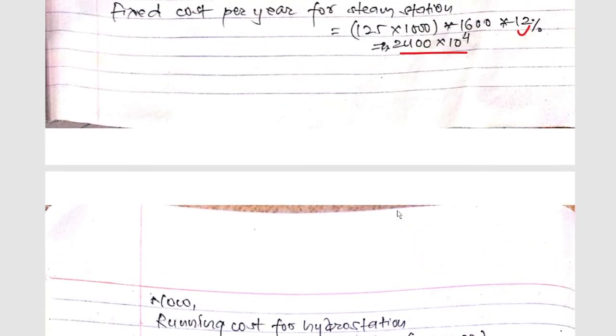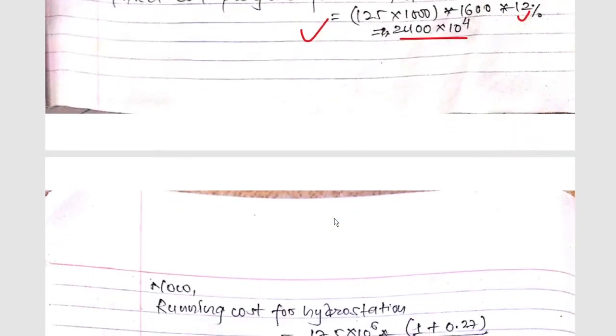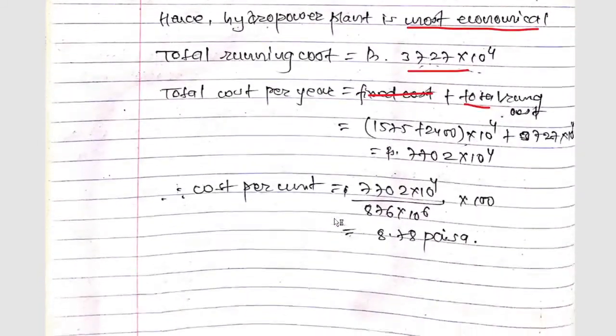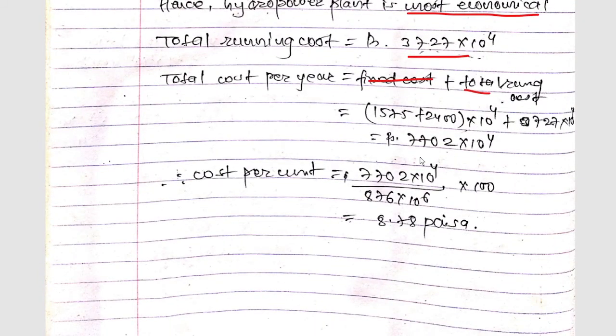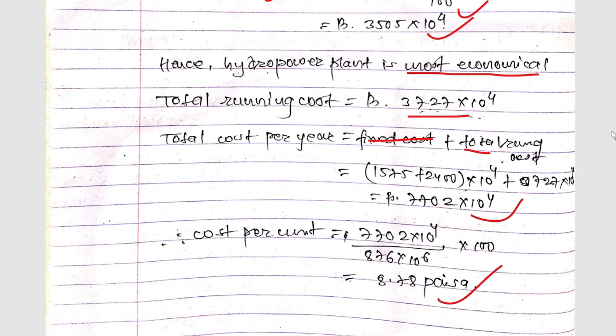The total cost per year for the combination is fixed cost plus total running cost = 7702×10⁴ rupees. Therefore, cost per unit = (7702×10⁴ × 100) / (876×10⁶) = 8.78 paisa per unit. Comparing all four alternatives: steam = 9.4p, nuclear = 10.15p, hydro = 6.07p, and combination = 8.78p. The hydro power plant alone is the most economical. Hope you enjoyed the lecture — thanks for watching and please subscribe to the channel.